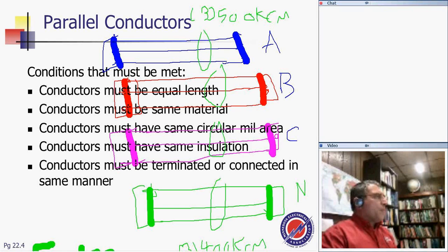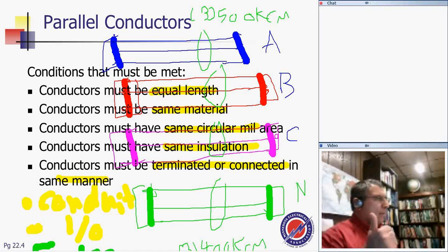A couple of things you must know. What does paralleling mean? Tie them at the end. We parallel because we can't carry the load with one conductor. A couple of rules. Number one, they have to be all the same length, same material, all copper or aluminum, the same size in kcm each, the same insulation, and also terminated with the same lugs. And I add one more, guys: the same type of conduit. If you put them in a conduit, it has to be the same conduit. And a third one, they have to be 1 aught or more. So, friend, to parallel conductors, you cannot parallel less than 1 aught. Same length, same material, same circular mil, same insulation, same termination, same type of conduit, PVC, rigid, EMT, and the conductor cannot be less than 1 aught.